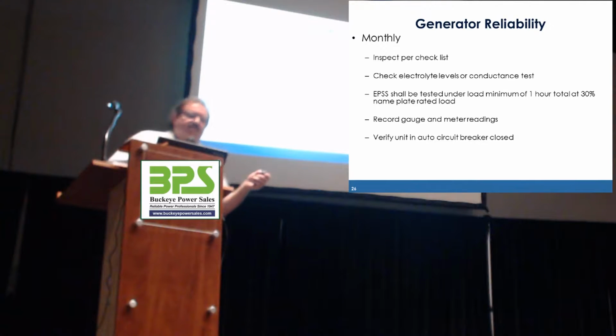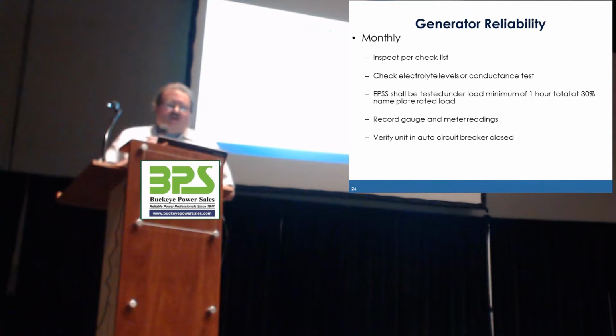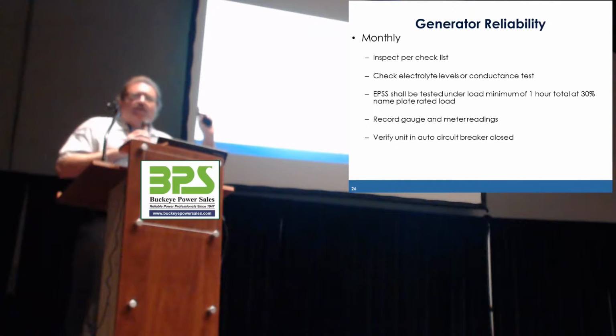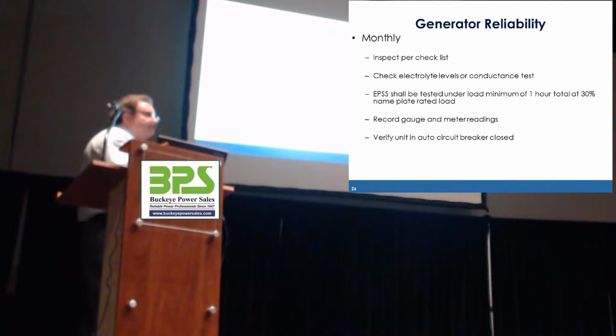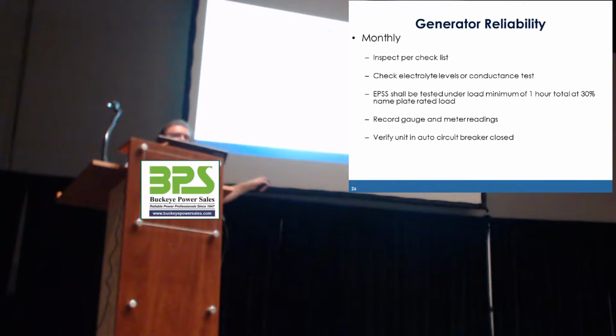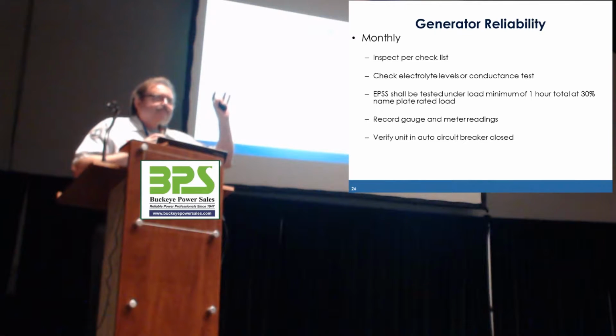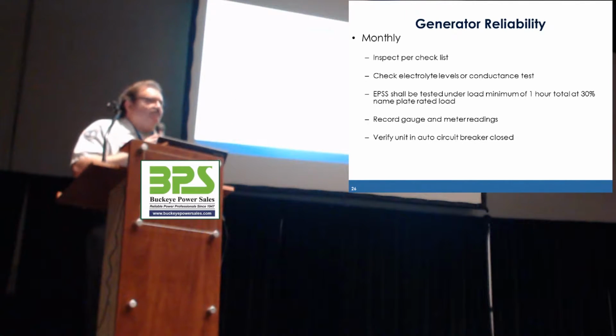Monthly, it also says that the EPSS, or the entire system, shall be tested under load a minimum of 1 hour at a minimum of 30% nameplate rated load. Now, most generators out there don't have 30% nameplate rated load on them, so we'll discuss what you have to do in this situation. But if this is an NFPA 110 site, we have to test this generator under load for an hour total. Okay? How many people here do that? Good, our same group here.